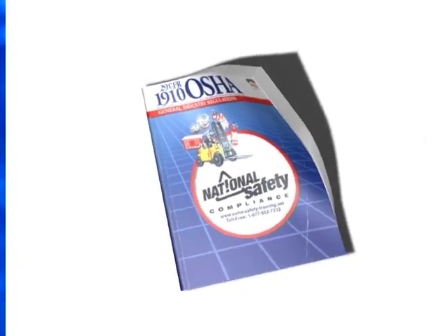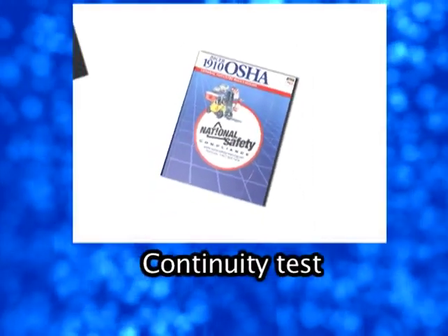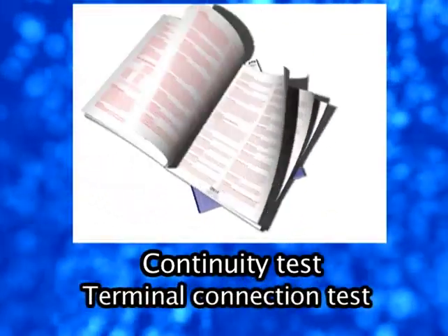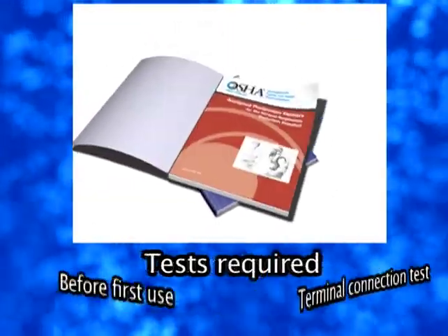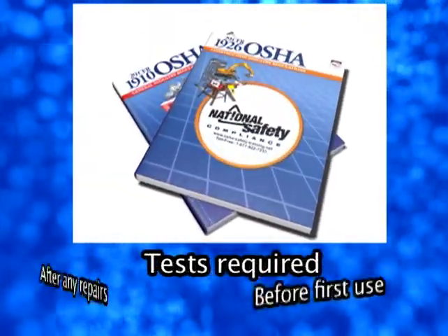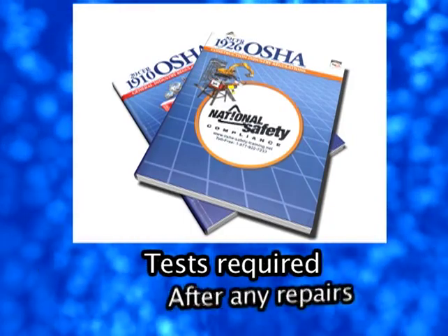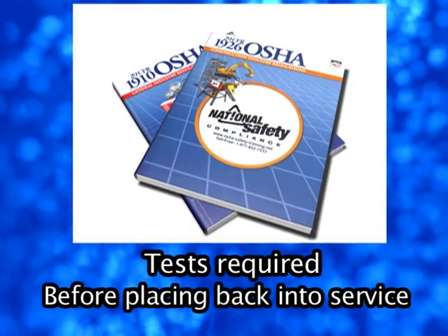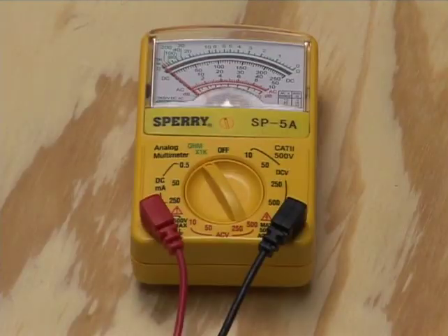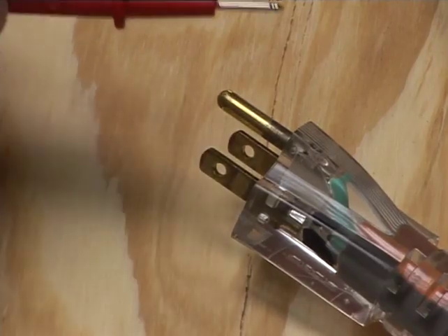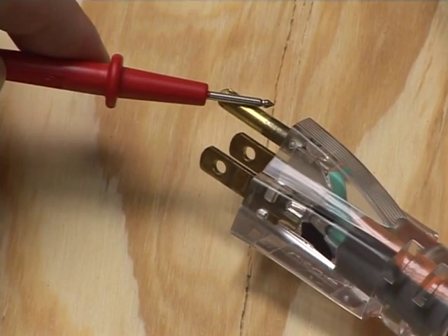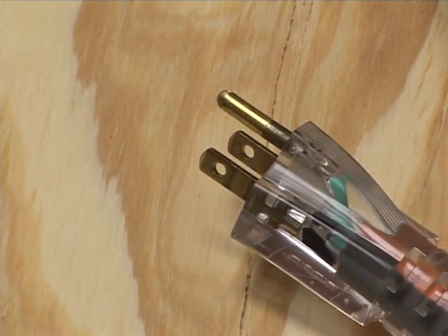OSHA requires 2 tests to be performed on electrical equipment: a continuity test and a terminal connection test. Tests are required before first use, after any repairs, and before placing the equipment back into service. OSHA also requires the tests to be performed after any suspected damage and before returning to use. Additionally, all equipment must be tested every 3 months, whether being used or not.